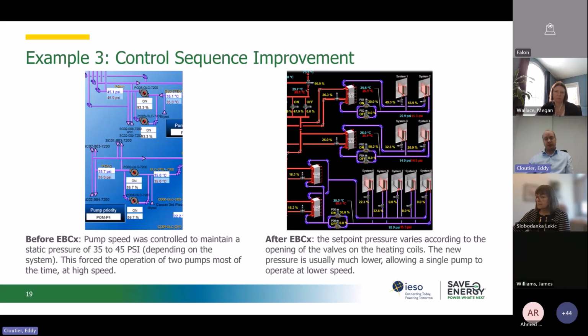Third example, about the operation of variable flow pumps, and we could also have had another example for variable flow ventilators. This is in a town hall. We had several air handling units heated by a hot glycol system. During construction, the control contractor had set the pressure set point too high to control the speed of the pumps, and we can see that here at 45 psi and 30 psi. And to reach this set point, the pumps had to run at high speed at all times, and even the backup pump had to run.